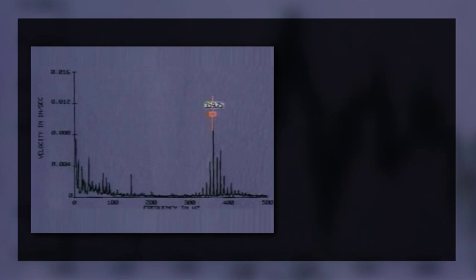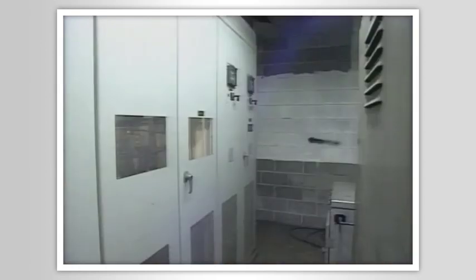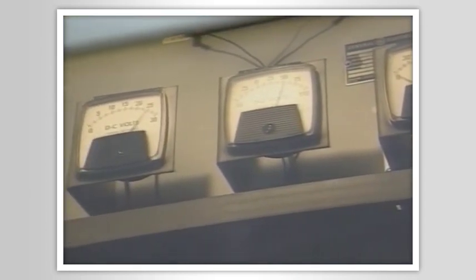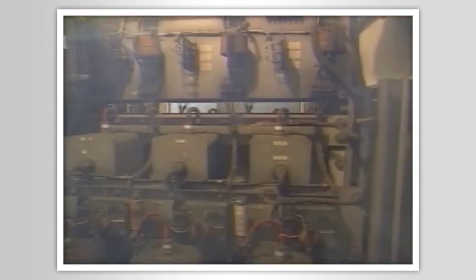There is something else here. Notice that the tallest peak is found at 359.75 hertz, or very nearly 360. After you've accumulated a little experience, you'll recognize this pattern right away. Anytime you find a peak at 360 hertz and side bands of turning speed, look for a DC motor. Silicon control rectifiers, known as SCRs in the motor control center, convert the incoming AC voltage to DC voltage by performing a full-wave rectification. Since AC voltage in North America is supplied at 60 hertz, and many DC motors have six poles, a peak at 360 hertz is very common.